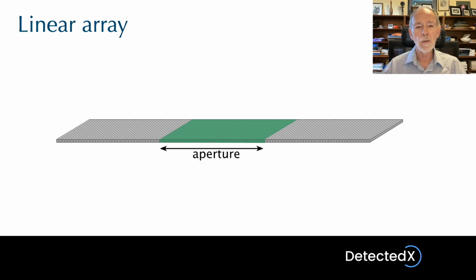You may be able to see how the machine can scan the beam. This block of transducer elements can be moved. It can be shifted from the left to the right-hand end of the probe, always keeping the same size, so that the aperture can be shifted up and down along the length of the transducer in order to move the beam to different positions. And we'll see later on this is exactly what the machine does.